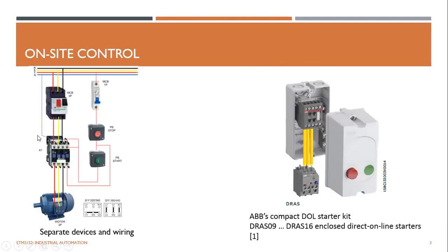Okay, so we can now see the two types of control. The first is starting with the on-site control, which means you have the motor and you have this main circuit breaker and the contactor. So the controlling is done locally, which means the operator has to sit close to the motor, like the control cabinet is located close to the motor. And the other one is the off-site control, which I will discuss in a few minutes.